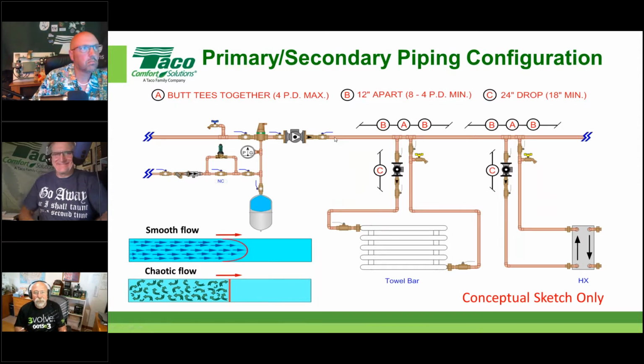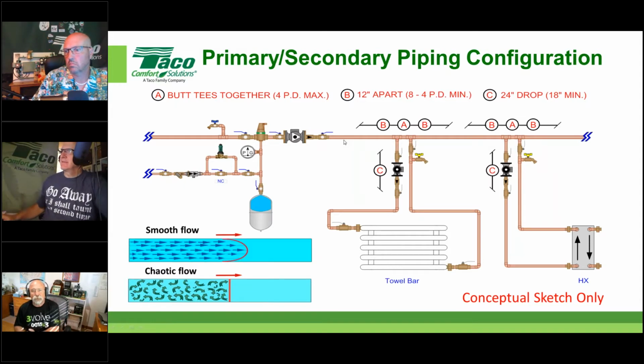Chaotic flow comes out of here. Some people say turbulent, but it really doesn't meet the turbulent flow criteria, so call it chaotic flow as it comes out of the circulator. After a certain amount of straight pipe length, it mellows back down to somewhat of a smooth flow - not truly laminar flow either, but we just want to give you a visual indication. What we're trying to achieve with that certain amount of straight pipe before those T's is we want it to be nice and smooth as it goes across these two T's.